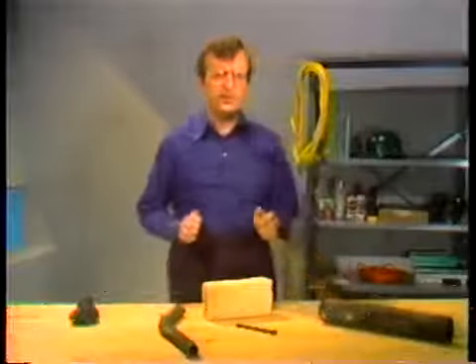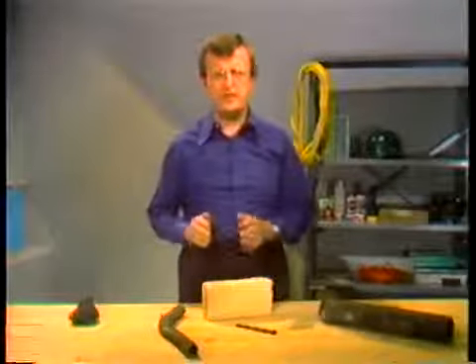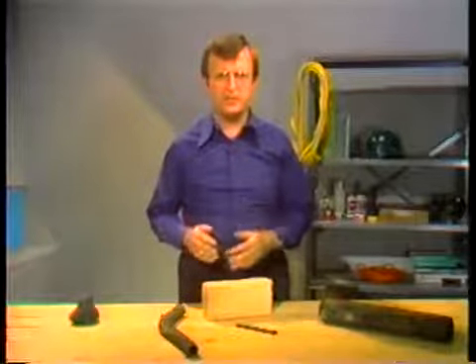Now, what we're going to be talking about here is how to detect potential problems during a routine fireside inspection. That means we'll be inspecting the surfaces inside the boiler that are exposed to fire and hot gases. Even though you're not the official boiler inspector, the work you do allows you to detect certain problems that can affect boiler reliability and efficiency, if you know what to look for.